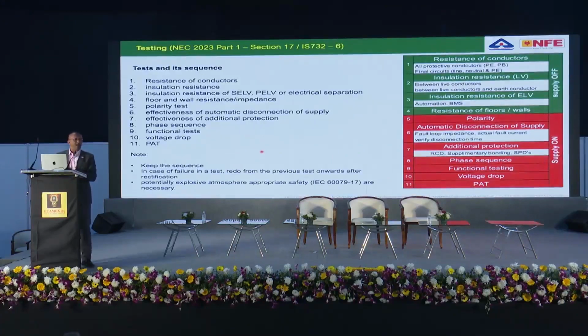Then inspection is followed by testing. There are 10 tests plus an 11th, which is a PAT test. The 10 tests ensure that your building is in very good shape. It is electrically safe. The 11th one ensures that the equipment which is connected is also safe. You can find all this information in NEC. Basically, NEC is a code of practice which is made mandatory. It talks about design, selection, erection and verification of an electrical installation to make an electrically safe Bharat.